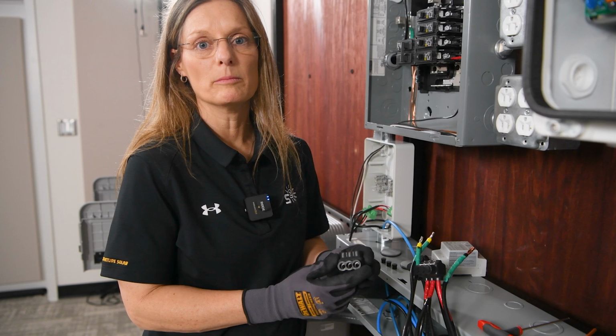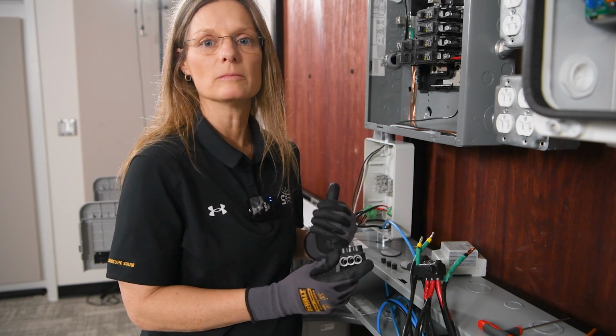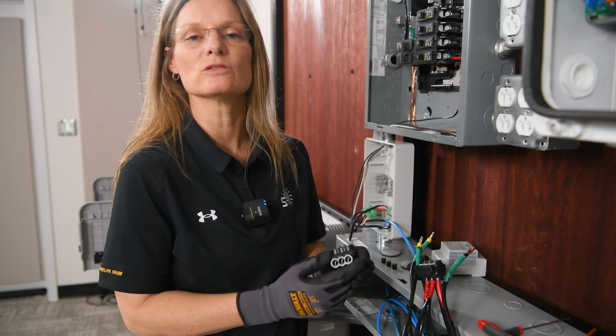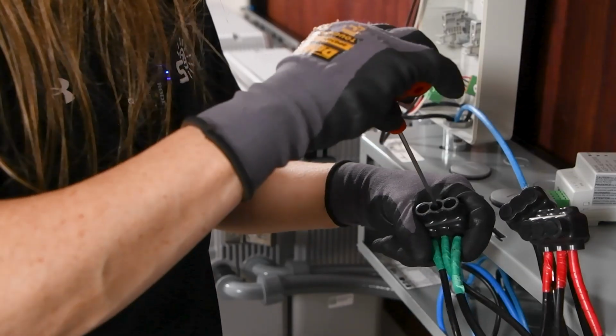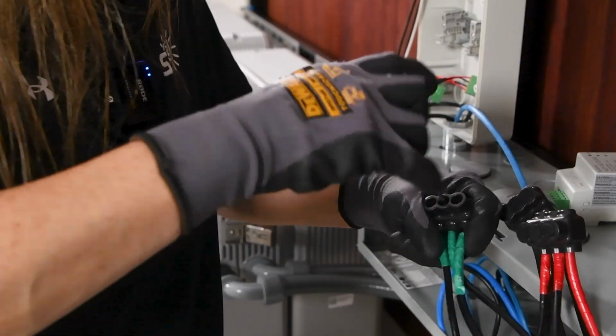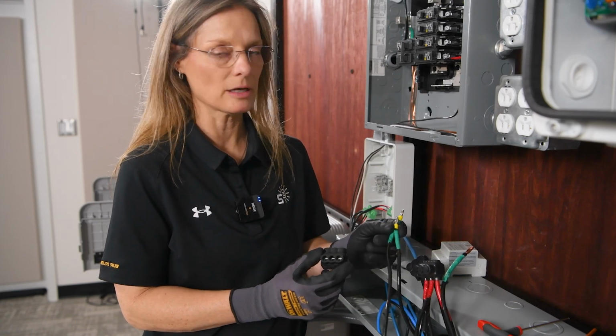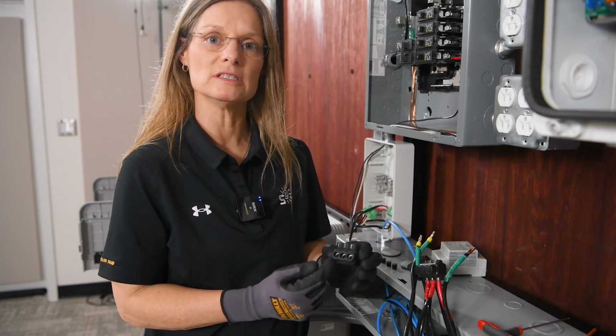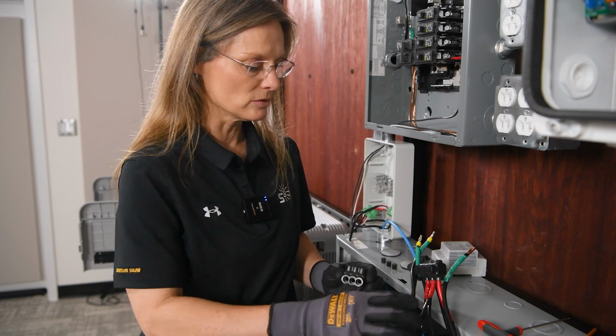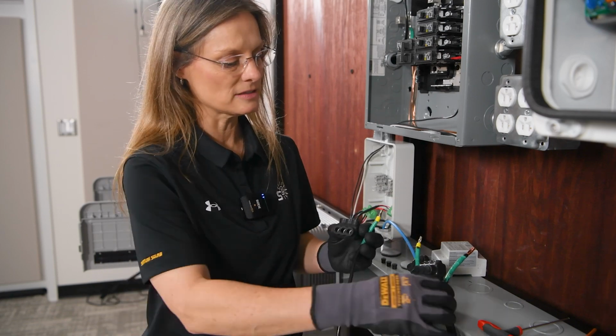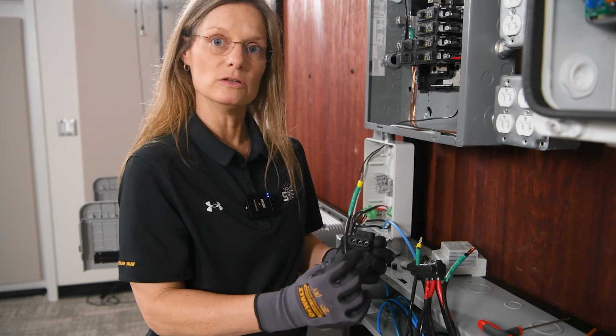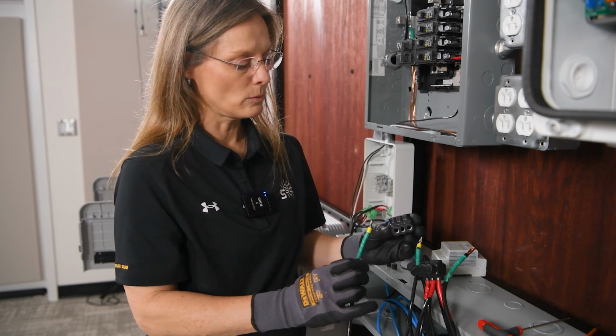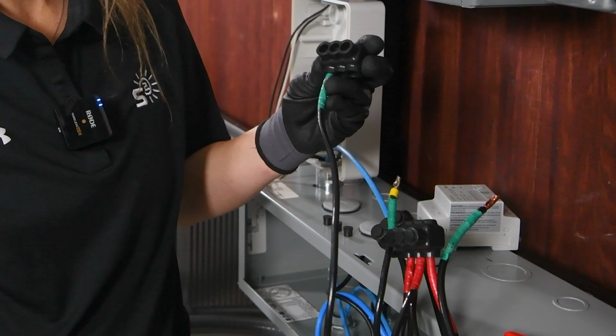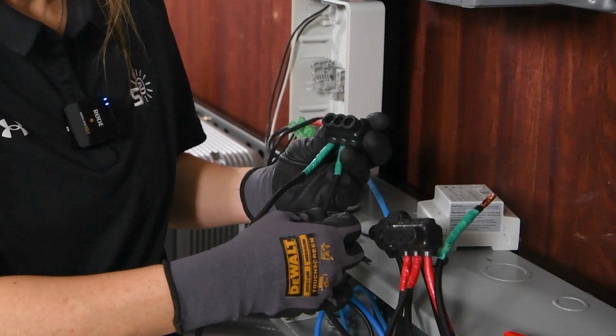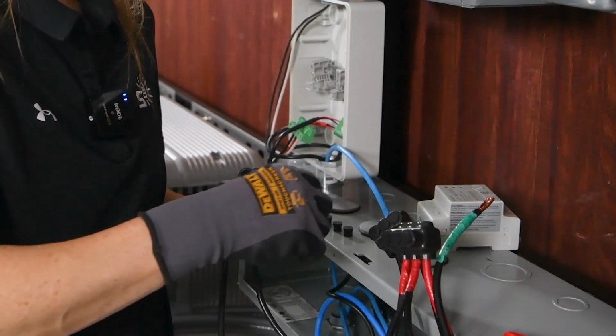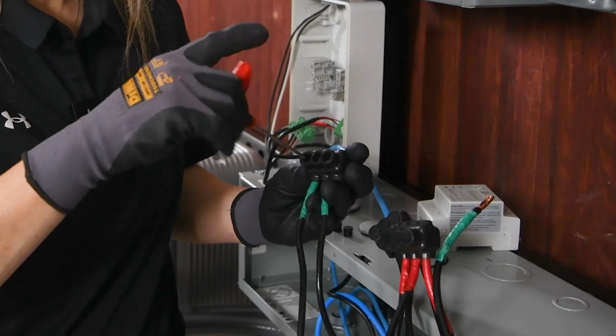One of the ways that we're combining the power cables for our batteries, because our inverter only has one input for batteries, is that we're using a mechanical lug with multiple inputs to be able to combine our power cables. This is also known as a multi-tap or a Polaris connector. And what we'll do is we've already ferruled some of these ends. They do not have to be ferruled, so you can either use them with ferrules or without. But what you can do is insert battery 1 power cable, battery 2 power cable, and you can tighten these down with your hex nut.